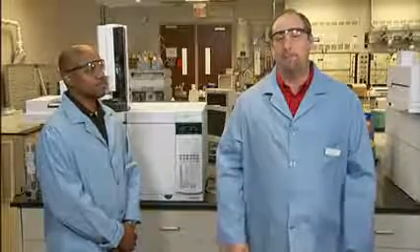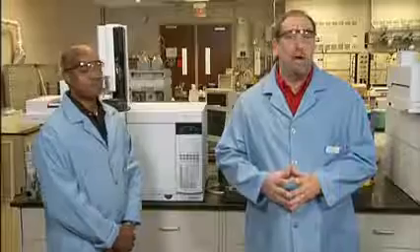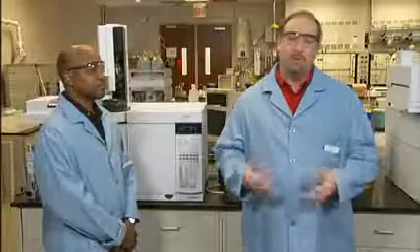The only real way to get them out is to bake out your column. You can take the column out and solvent rinse it, but most people aren't doing this because of the time required. Typically, bakeout times are one to two hours. Longer times can be used, but based on the volume of the column and the flow rate of the gas during bakeout, you should be able to get most of the things that will come out within the first two hours of bakeout.